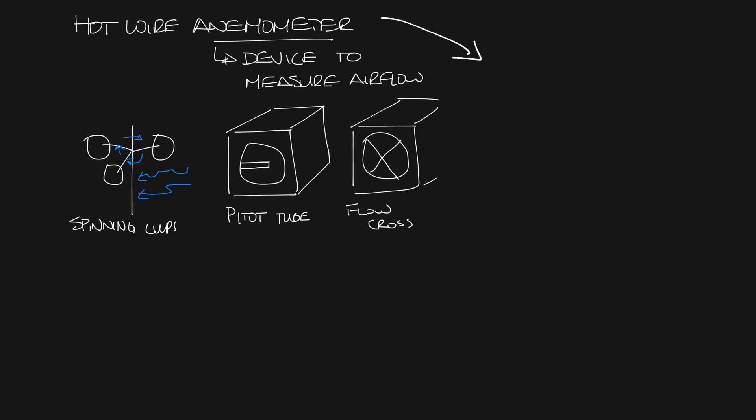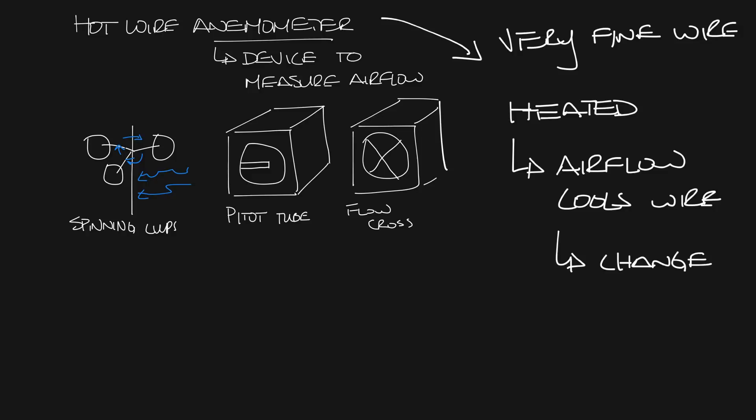A hot wire anemometer is pretty much what it sounds like. It's a very fine wire that is heated and put in airflow. Air flowing past the wire cools the wire down. Since the electrical resistance of the wire changes with temperature, you can use this change in resistance caused by the temperature drop to calculate the airflow across the wire.